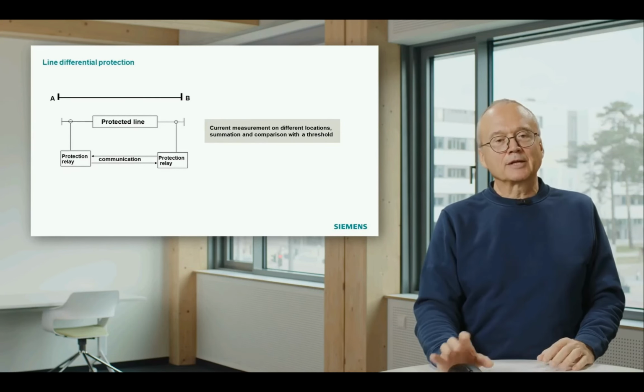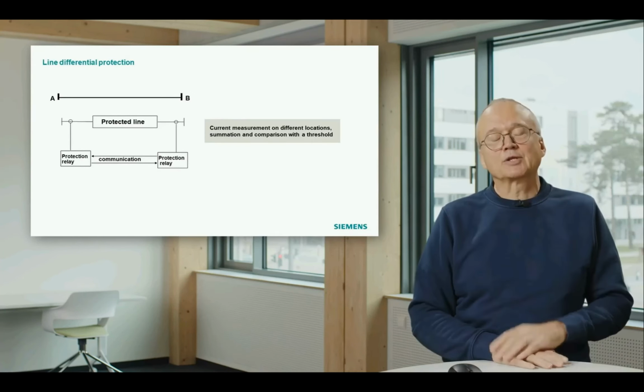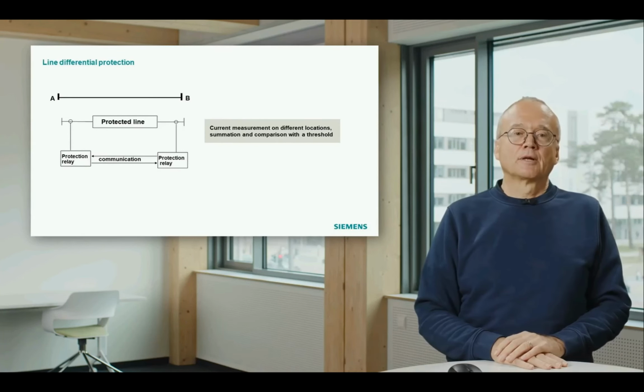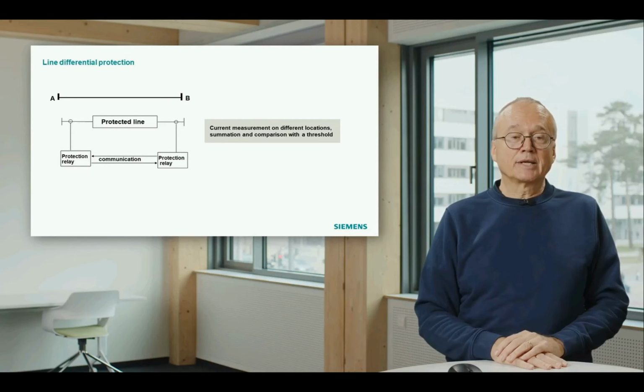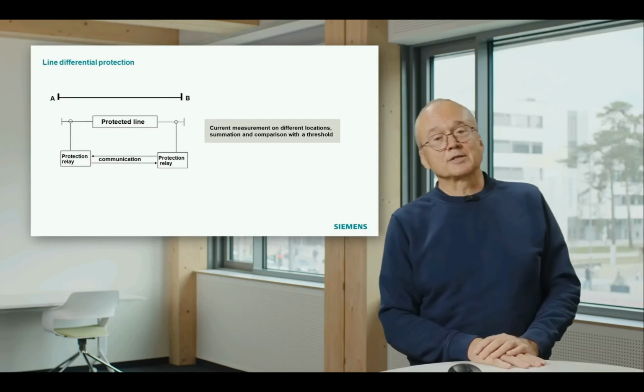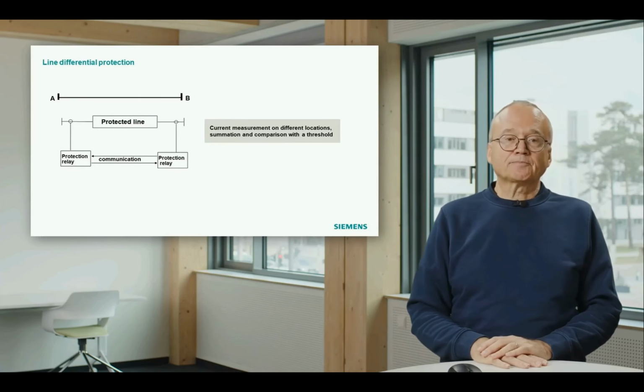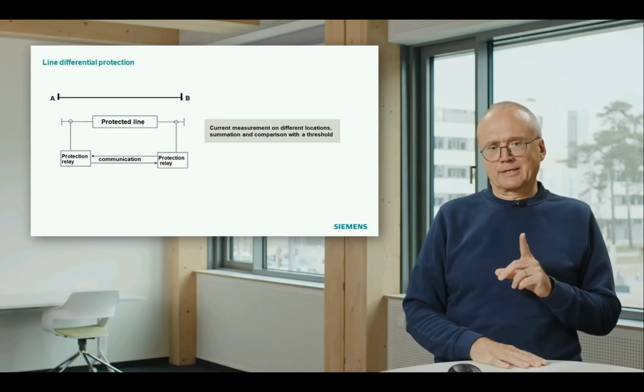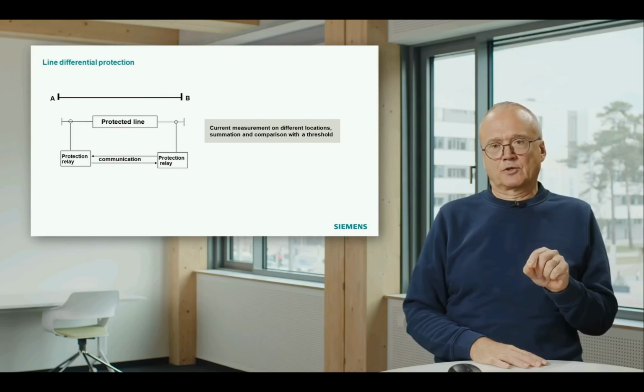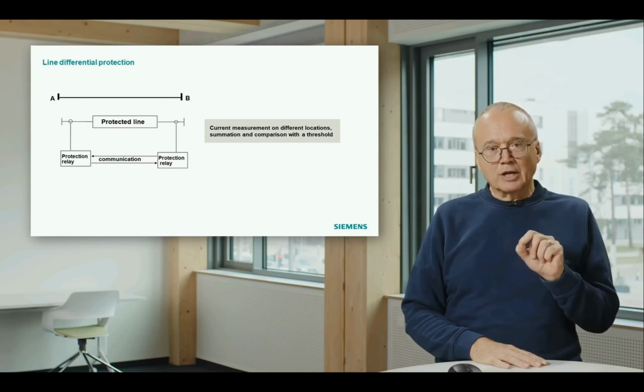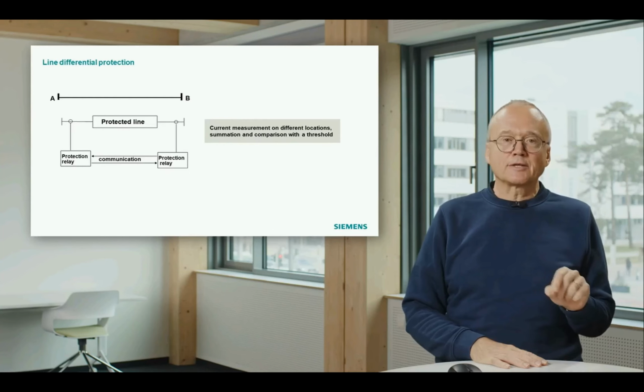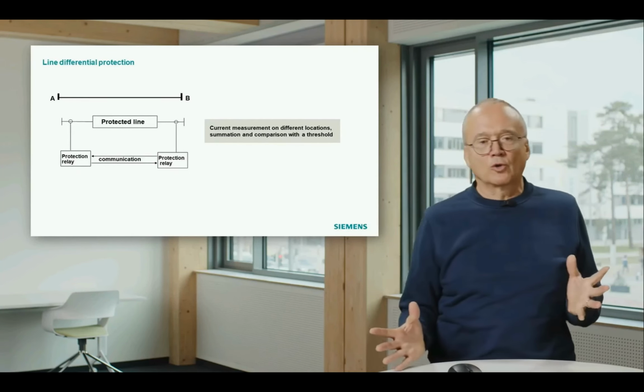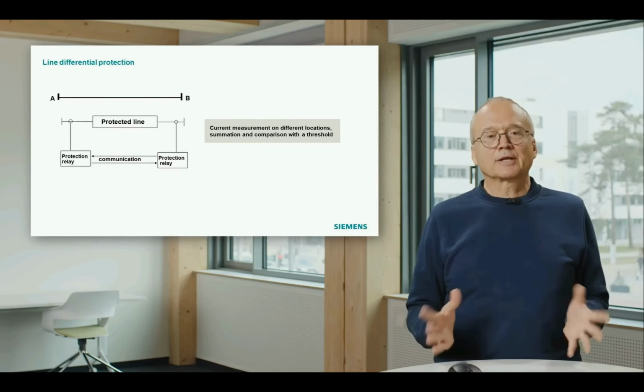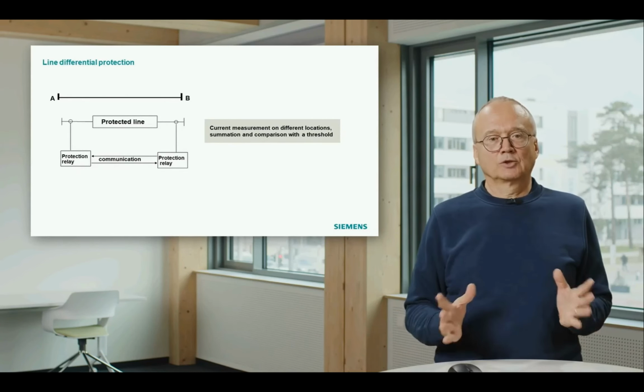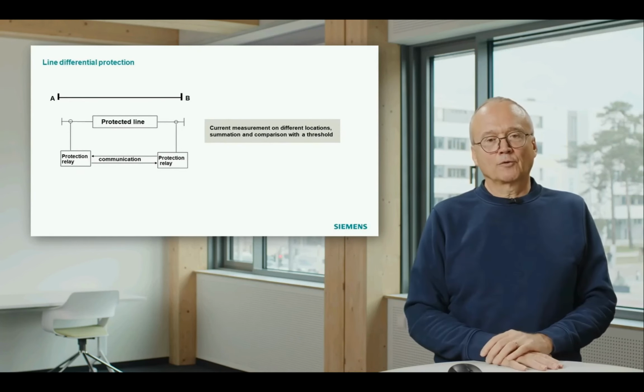That means a differential protection, a differential line protection always needs communication between the two or even three devices if we have a three-terminal line. And this communication, and that is important, is part of the protection system. It must be a reliable communication, because as soon as the communication fails or something goes wrong there, this protection doesn't work any longer. Communication is part of the protection.